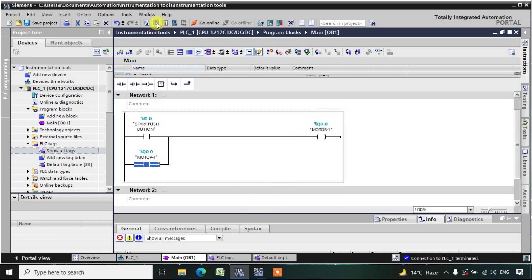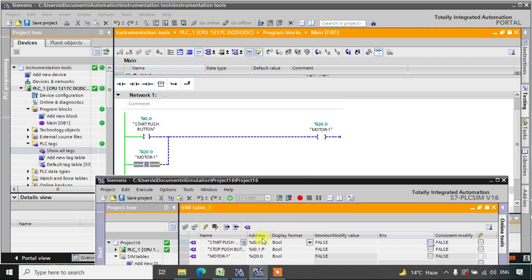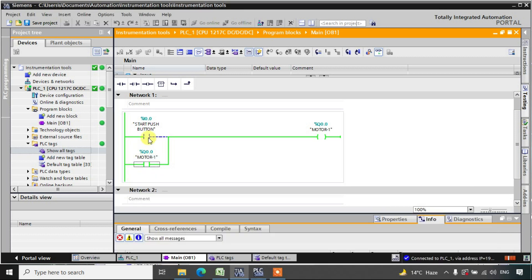Let us download this logic and monitor it. When you press the start push button, power is also going from the parallel NO branch. Because of the output address being high, this NO is also in the high state and supplying power. When you release the push button, no power goes from the start contact, but this NO is allowing the power to flow, so the output remains continuously in the high state.